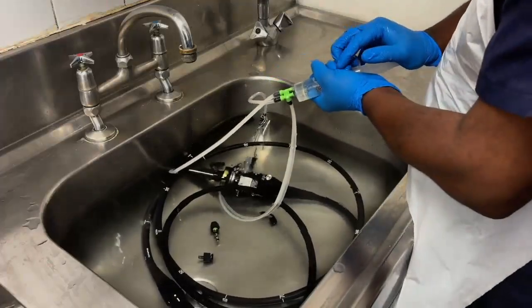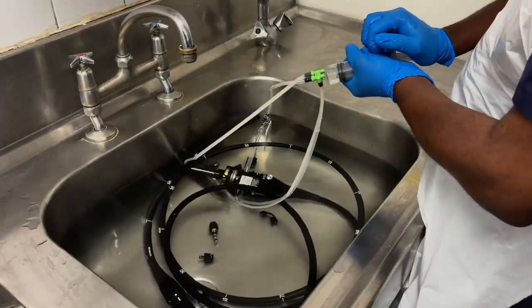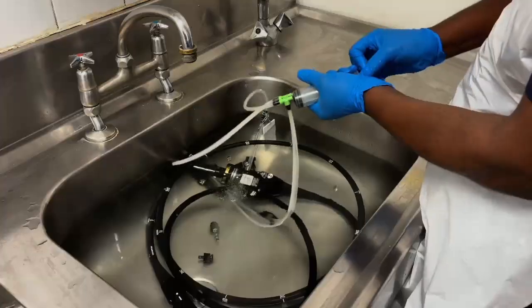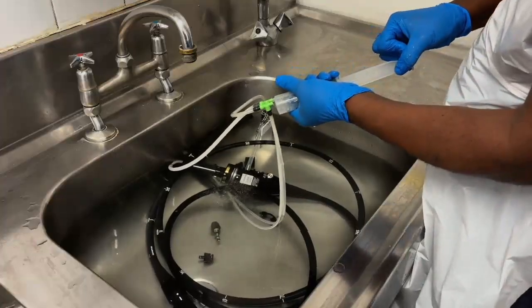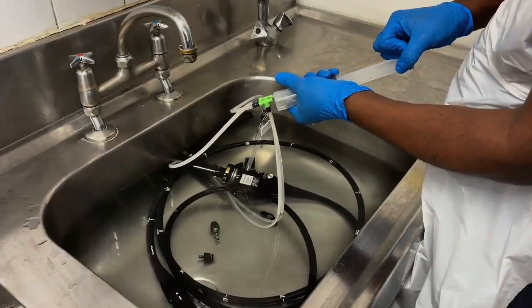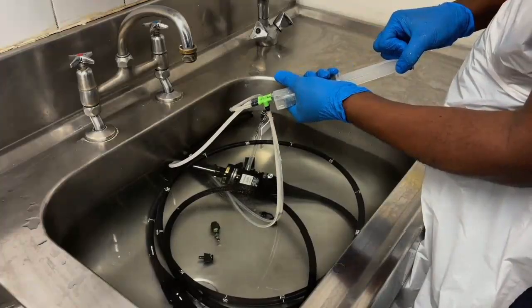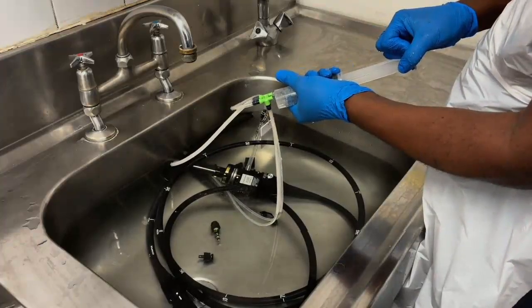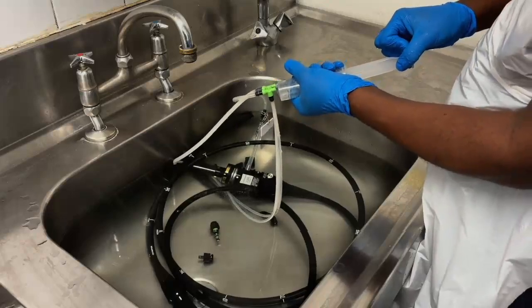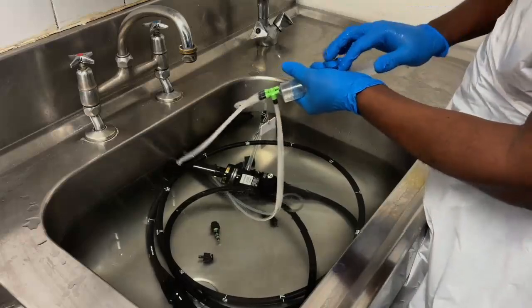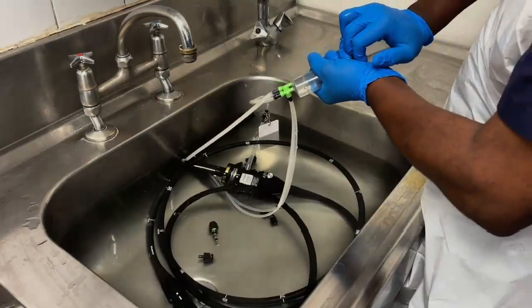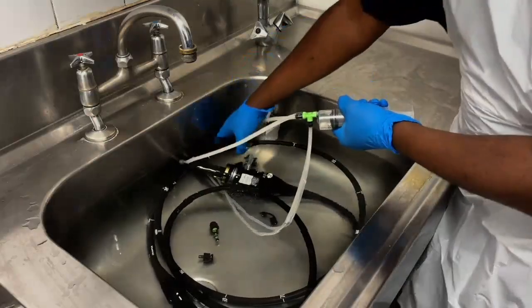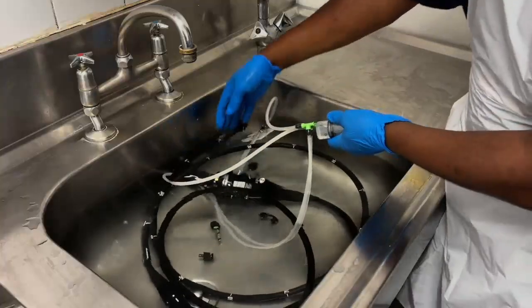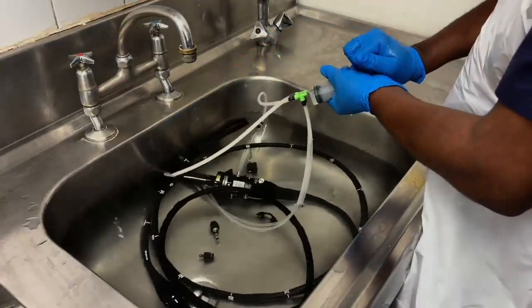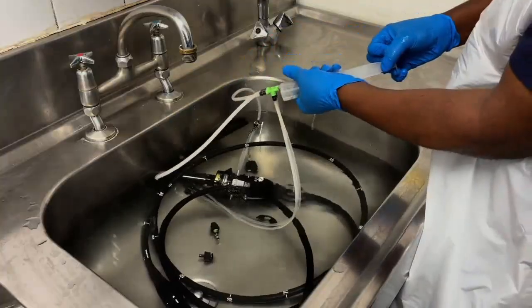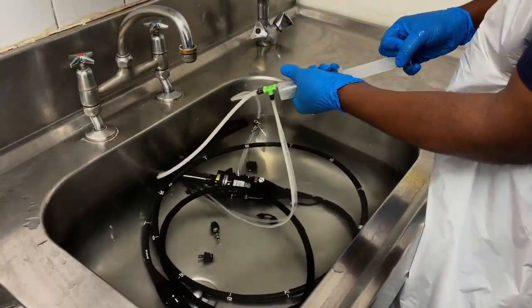The clean water helps to rinse out detergent residuals as well as potential contaminants. Remember, detergent residuals themselves can be problematic. They can cause infections in the patient. Thoroughly rinse each channel as directed by the manufacturer.